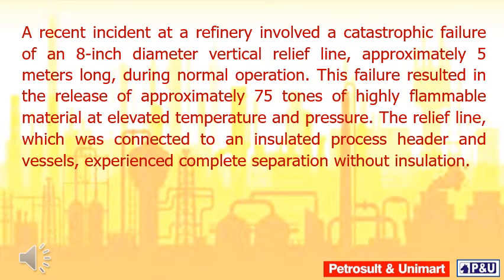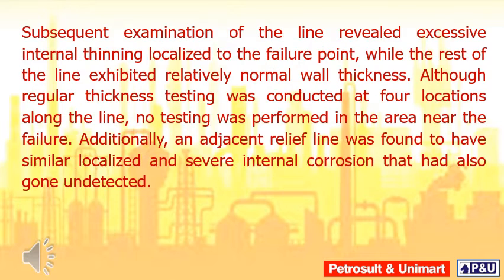A recent incident at a refinery involved a catastrophic failure of an 8-inch diameter vertical relief line approximately 5 meters long. During normal operation, this failure resulted in the release of approximately 75 tons of highly flammable material at elevated temperature and pressure. The relief line, which was connected to an insulated process header and vessels, experienced complete separation without insulation.